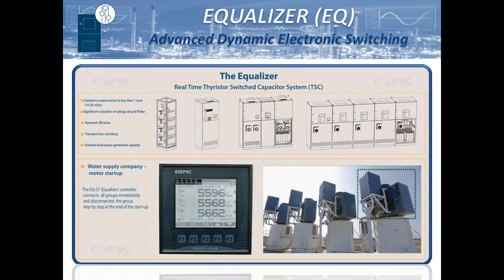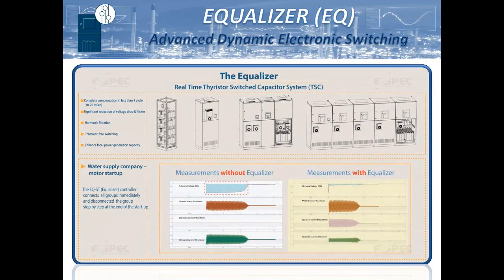The EQ-ST (Equalizer) controller connects all groups immediately and disconnects the groups step by step at the end of the startup. The voltage drop at the substation was improved from 10% to 2.4%. The current was reduced by 44% and the startup period from 4 seconds to 3 seconds.